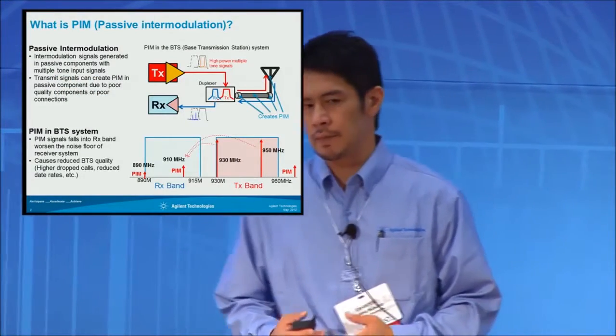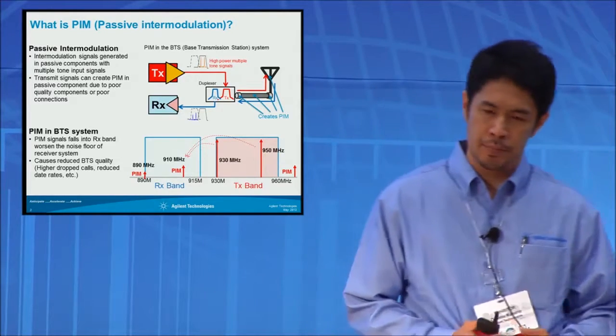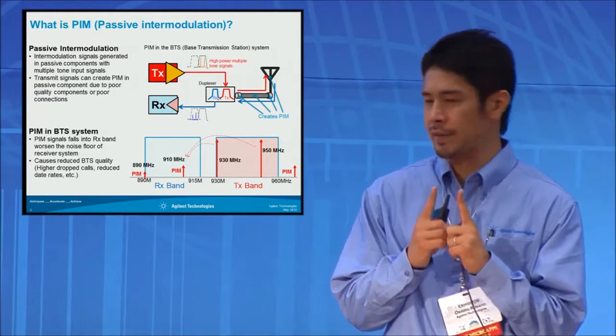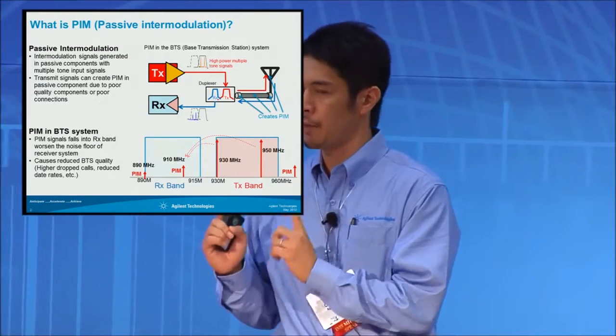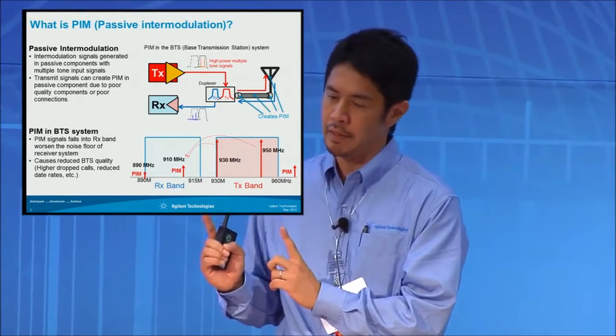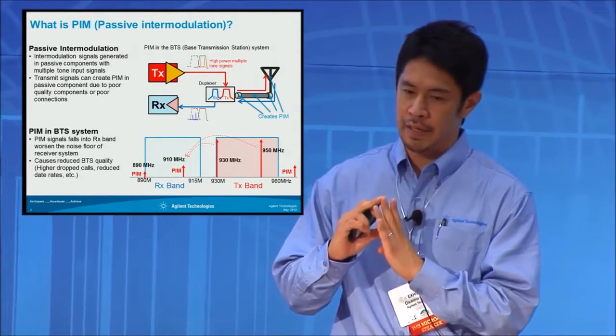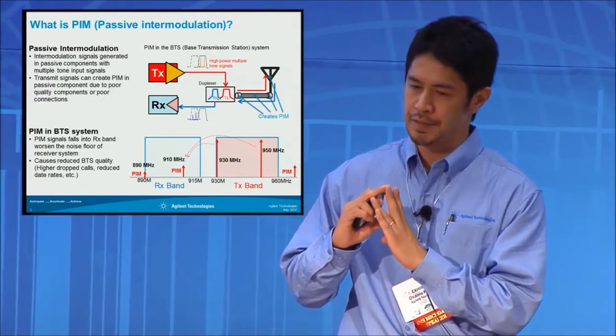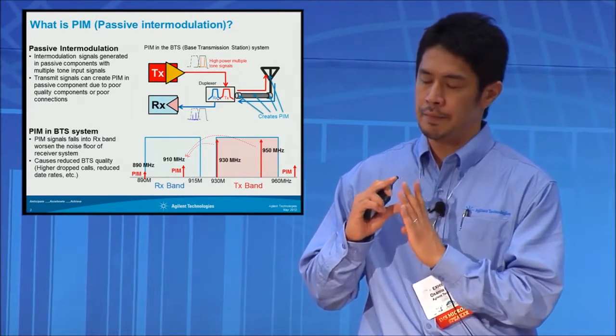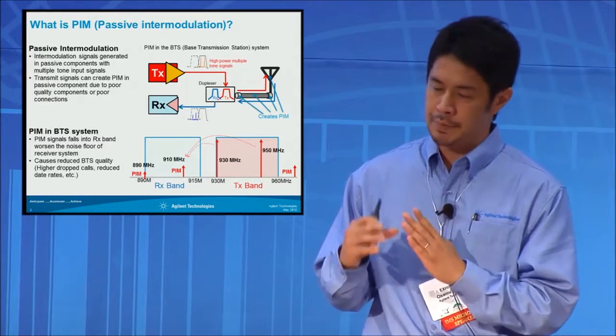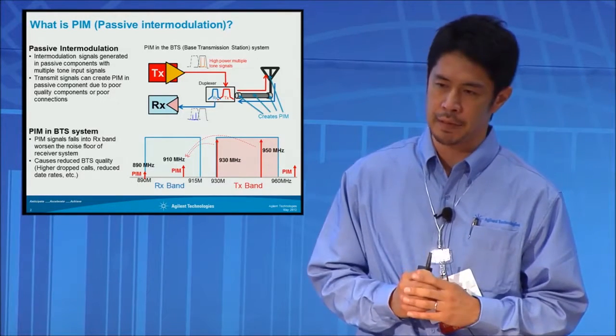Let me talk a little bit about PIM — passive intermodulation. If you put two tones to an active device, it can create intermodulation signals. Usually it is an active device that creates intermodulation signals. However, it is possible to create intermodulation with a passive device as well.